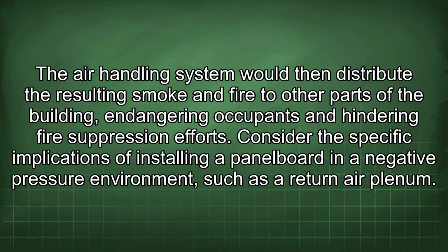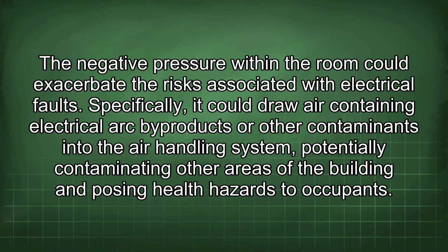Consider the specific implications of installing a panelboard in a negative pressure environment, such as a return air plenum. The negative pressure within the room could exacerbate the risks associated with electrical faults. Specifically, it could draw air containing electrical arc byproducts or other contaminants into the air handling system, potentially contaminating other areas of the building and posing health hazards to occupants.